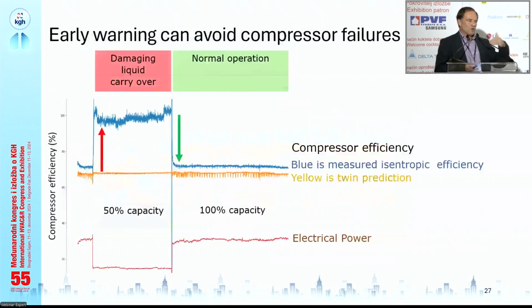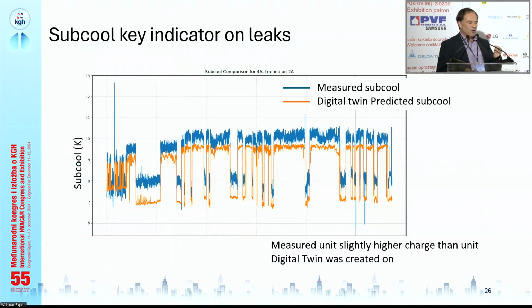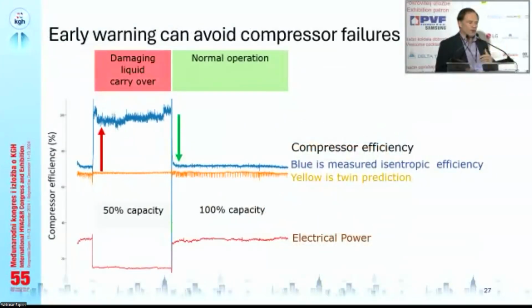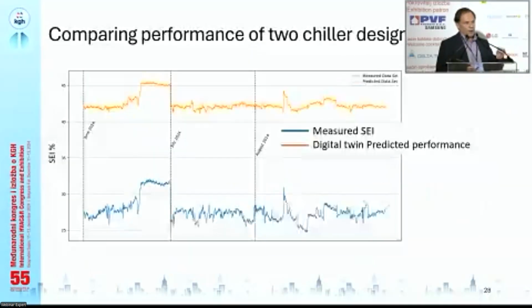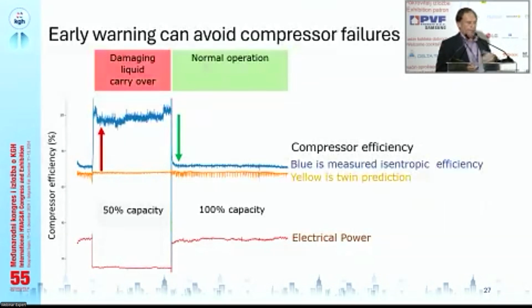This is showing compressor efficiency. There are thousands of compressors killed every year on this problem, where you get liquid carryover from either, these are tandem scrolls, and it leaks backwards through the standstill compressor, or you can have expansion device issues causing liquid return or excess oil transport, and you cool down the compressor. You see it immediately if you monitor it, and you can save the compressors. It's thousands of compressors destroyed every year on this.